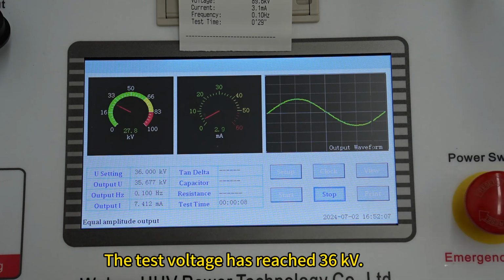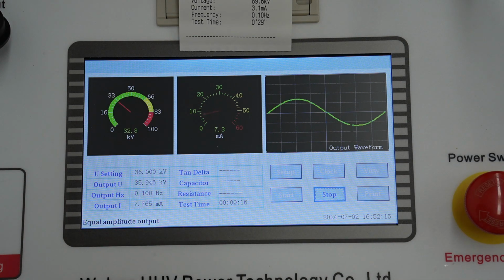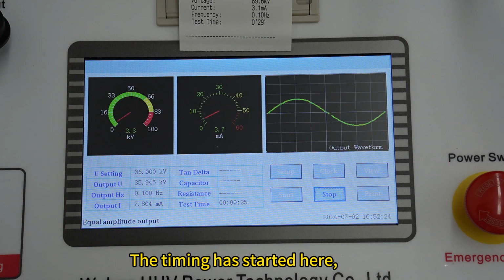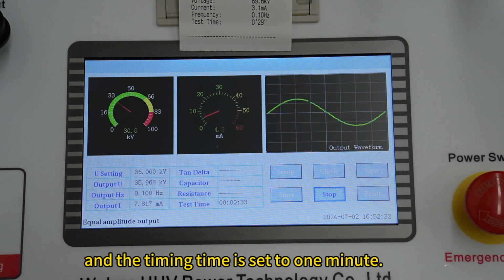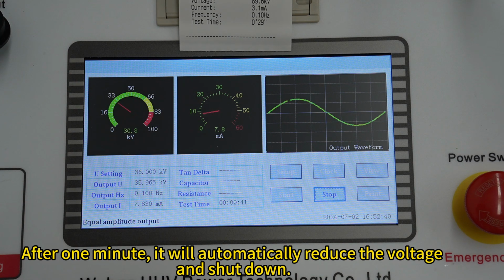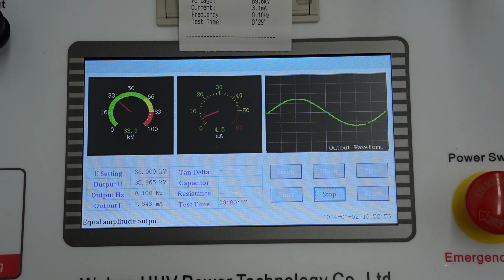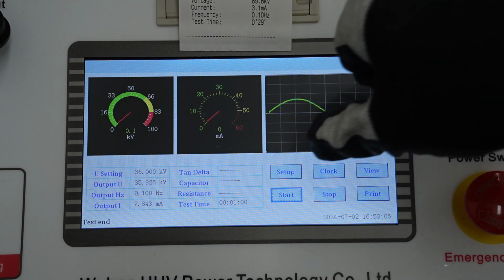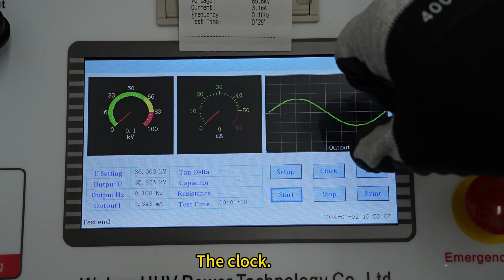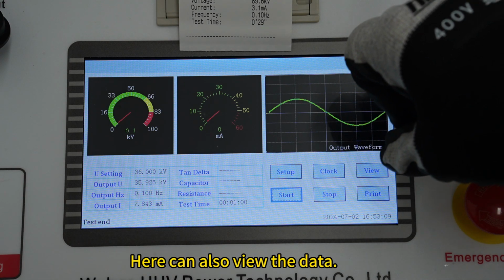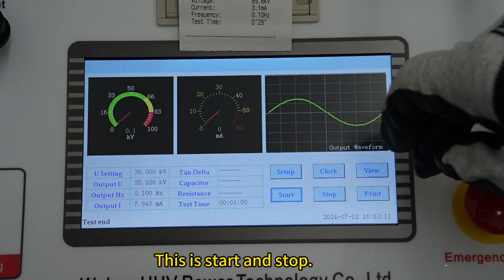The test voltage has reached 36 kV. The timing has started here, and the timing time is set to 1 minute. After 1 minute, it will automatically reduce the voltage and shut down. When 1 minute is up, it shuts down. This is the setting. The clock. Here can also view the data. This is start and stop.